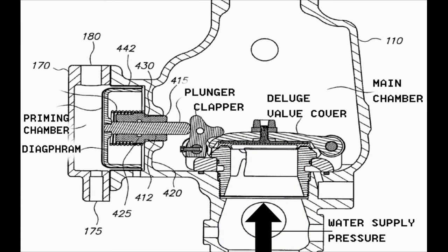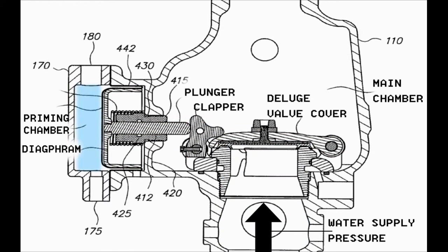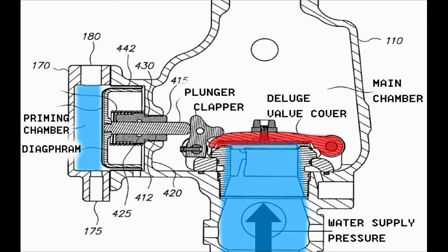In the shown figure, the deluge valve is in the normal closed position, where the priming water pressure is pushing the diaphragm in the forward position, which is connected to the plunger, forcing the clapper to close the deluge valve and overcoming the water supply pressure. Therefore, the priming water pressure behind the diaphragm is balancing the water supply pressure, causing the deluge valve to be closed.